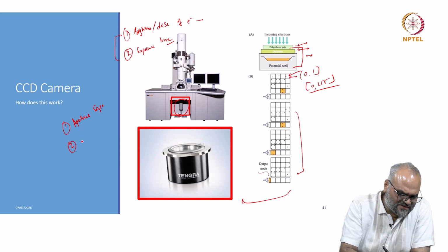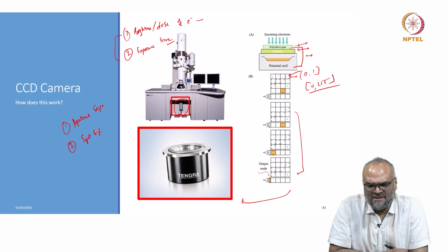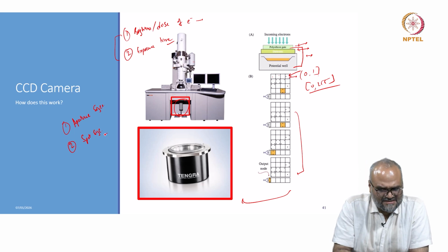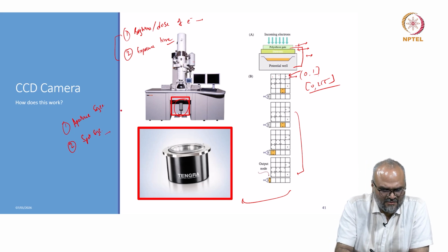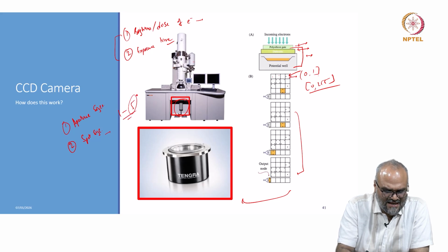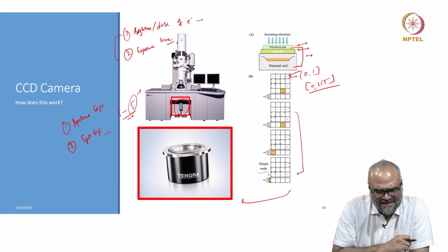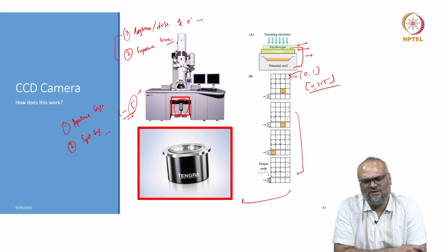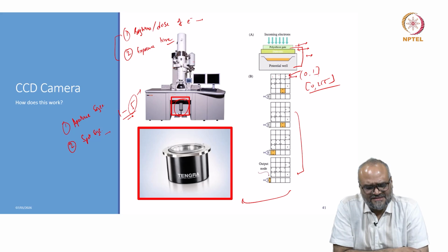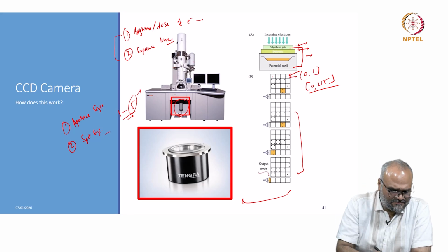You also control something called the spot size. Typically the spot size is counterintuitive. The numbers from 1 to 5 or 1 to 9, the larger the spot size is, the smaller the brightness or the beam current is.